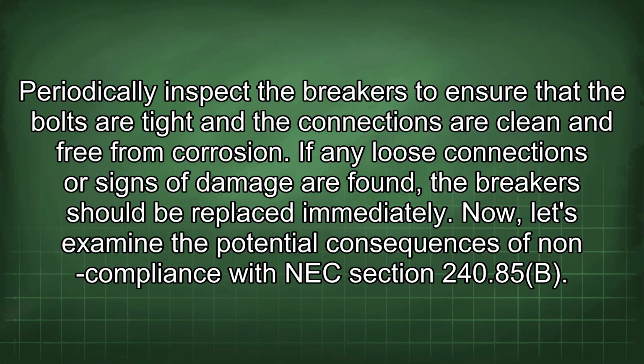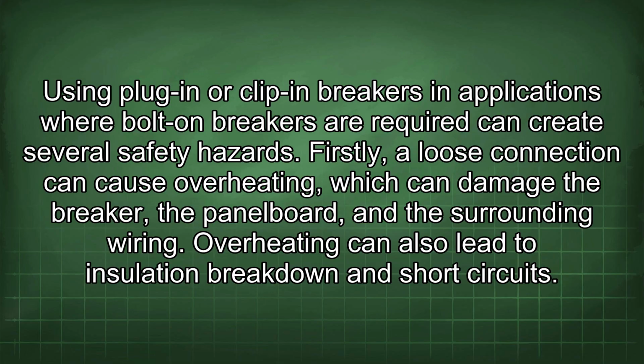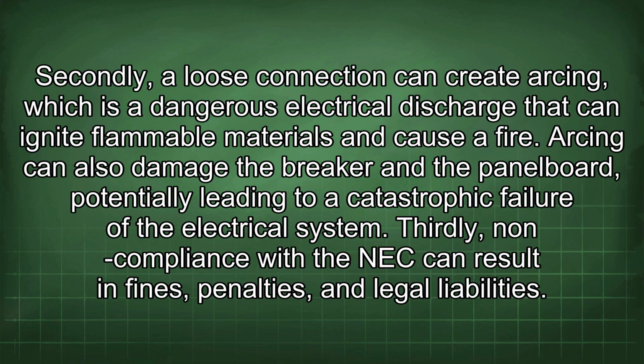Now let's examine the potential consequences of non-compliance with NEC Section 240.85b. Using plug-in or clip-in breakers in applications where bolt-on breakers are required can create several safety hazards. Firstly, a loose connection can cause overheating, which can damage the breaker, the panel board, and the surrounding wiring. Overheating can also lead to insulation breakdown and short circuits. Secondly, a loose connection can create arcing, which is a dangerous electrical discharge that can ignite flammable materials and cause a fire. Arcing can also damage the breaker and the panel board, potentially leading to a catastrophic failure of the electrical system.